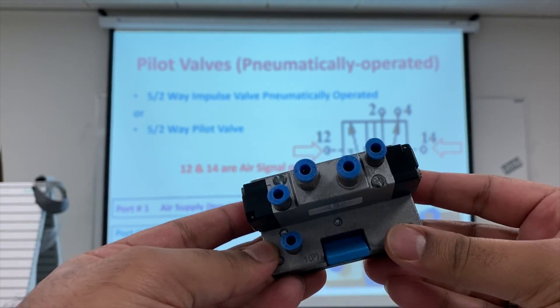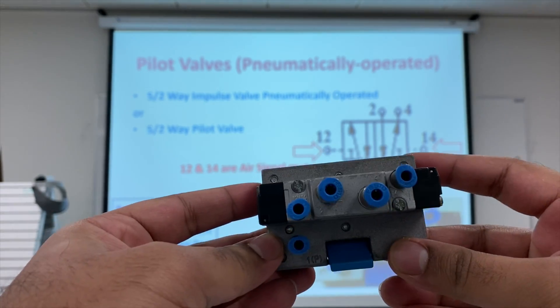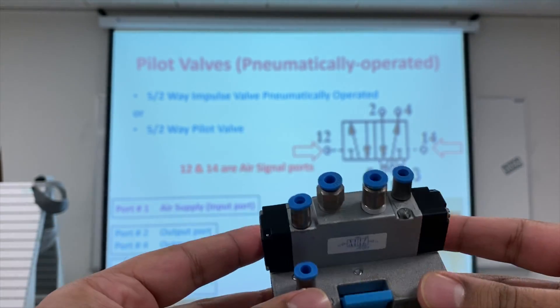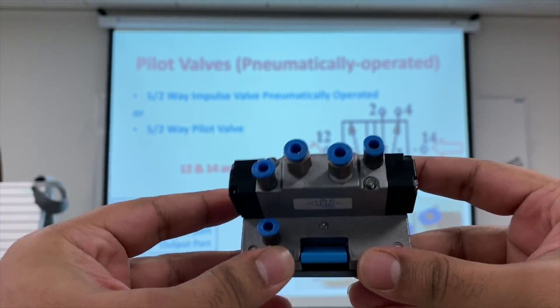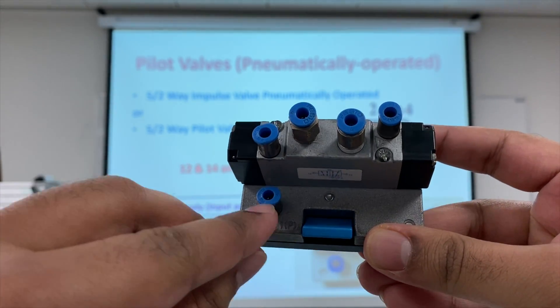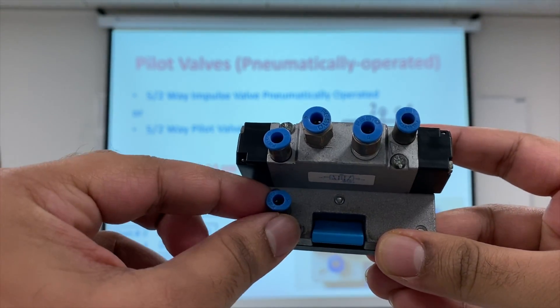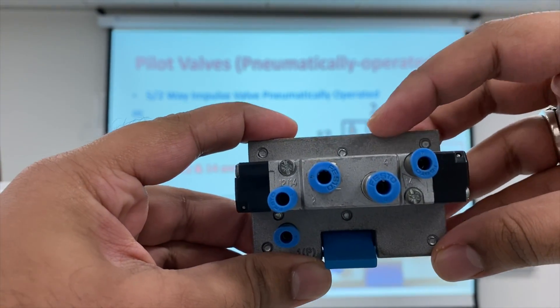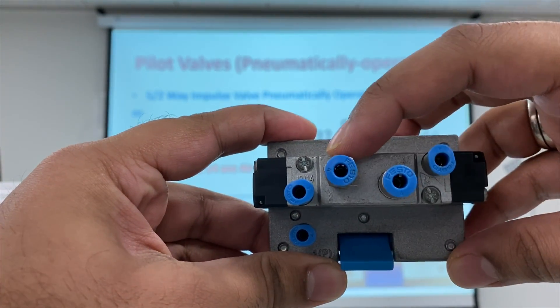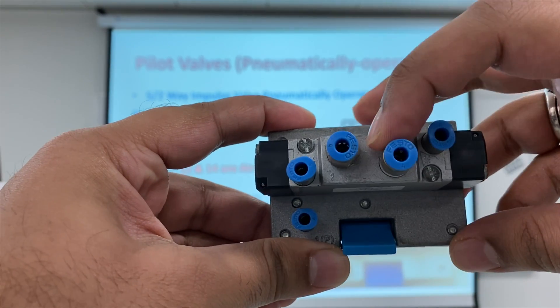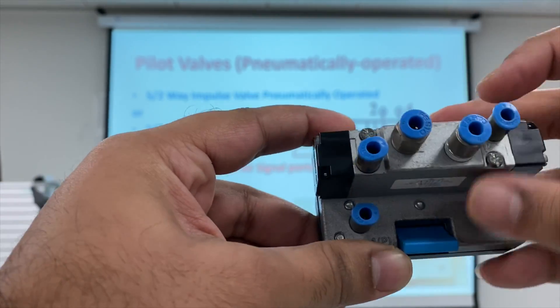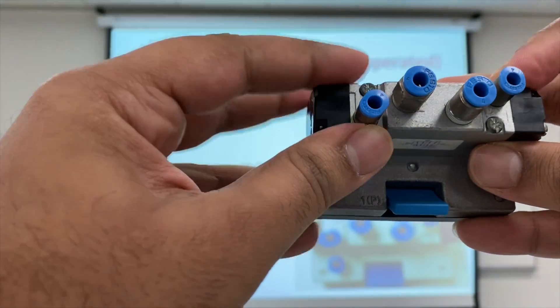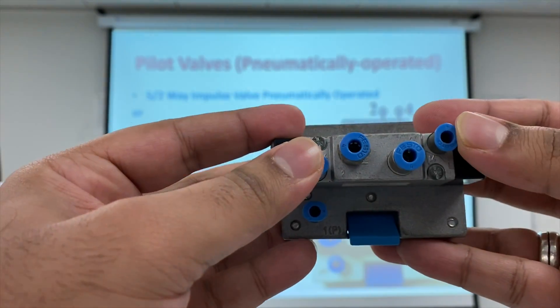What you see in front of you is the five-by-two way pilot valve, or five-by-two way impulse valve. This is port one, where the air supply is connected. Over here we have port two and port four — these are the output ports. And these two ports are port 12 and port 14 — these are the signal ports.